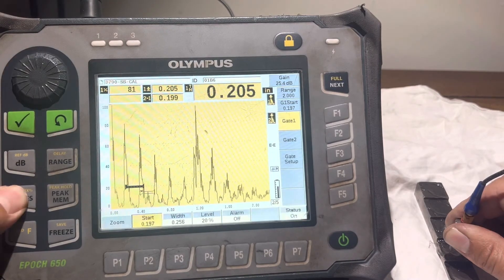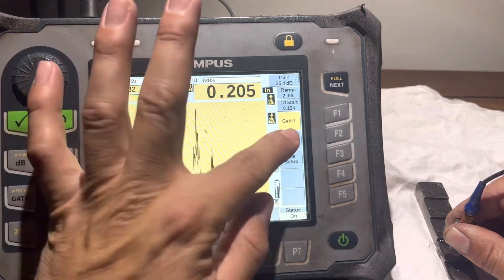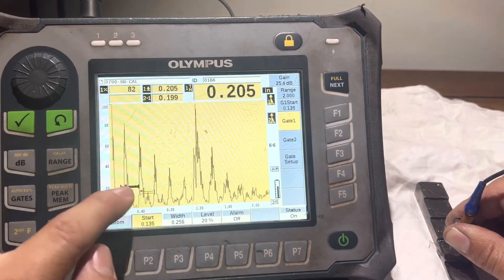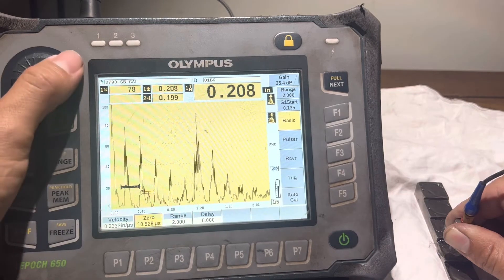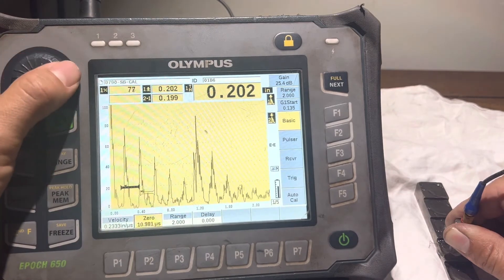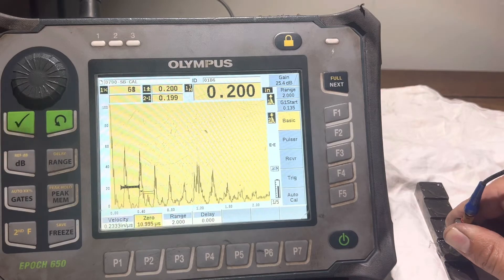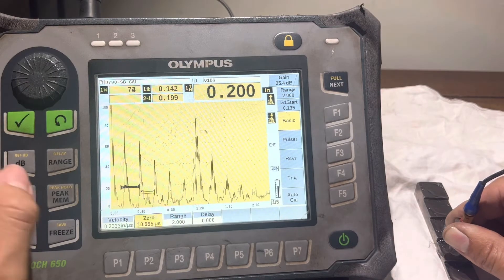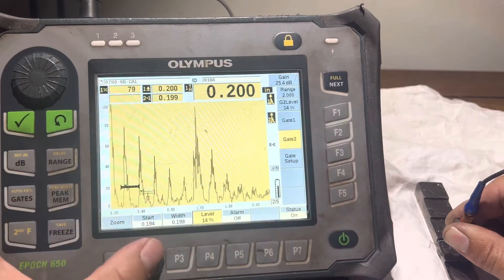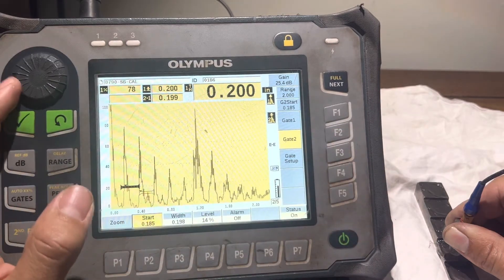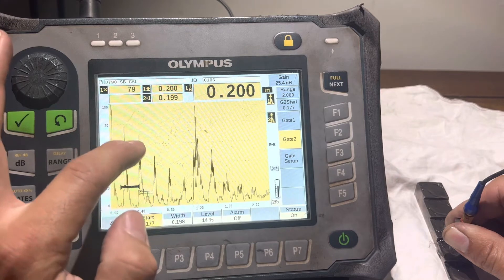It's out of range, so I'm going to move my gate 1 into place right on the center, hit back, and there we go there is the 2. My gate 2 is in place as well right on the center, it's reading the highest peak.